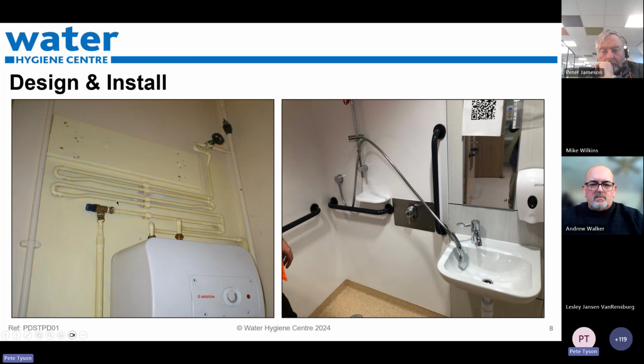On this one, we've got a radiator-like type design. Somebody had asked for this to be installed because they wanted to dry their towels on this concoction of metallurgy and pipework. When asking a contractor to do that, they should be competent enough to say that's not quite right - we shouldn't be elongating pipework or giving it areas where it could stagnate. So there were lots of things that could and should have been said before this was even installed. We've got to make sure the individuals asking for this extra, and the person installing it, are fully aware of the implications of doing it.